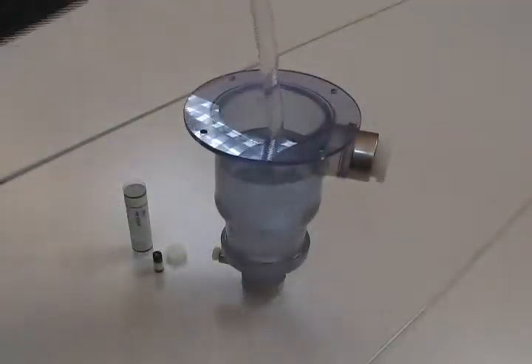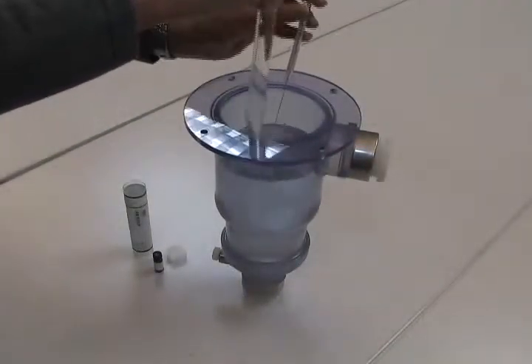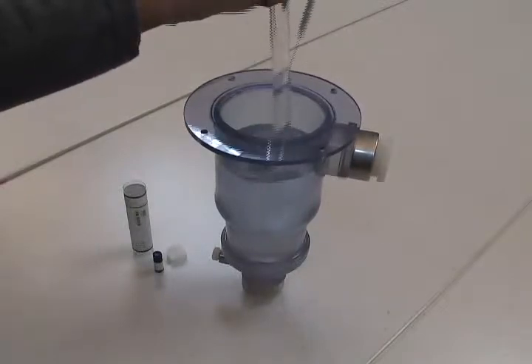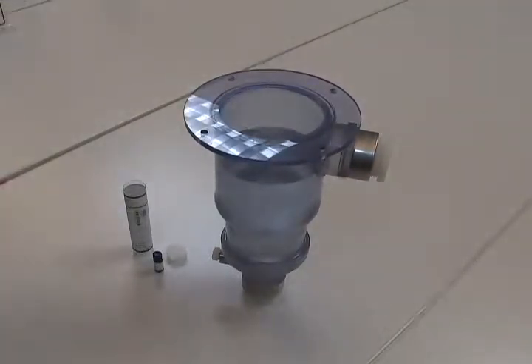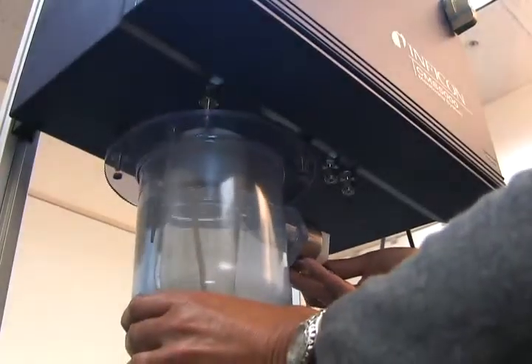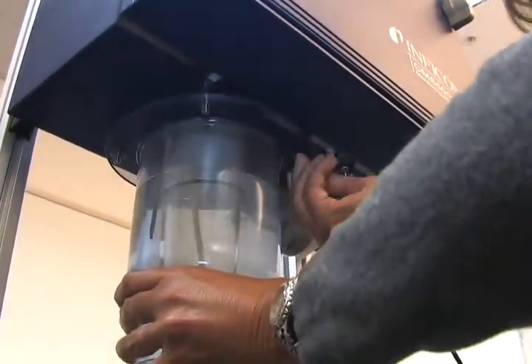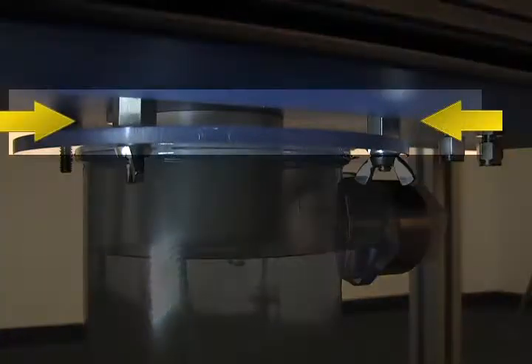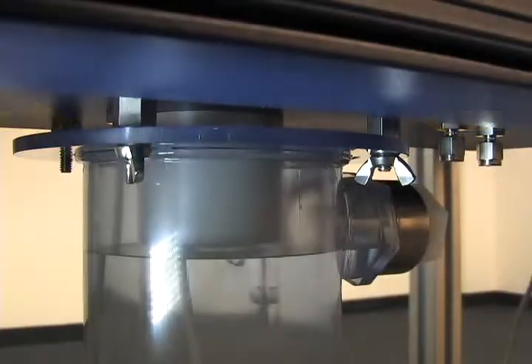To prepare the calibration standard, the 1-liter sample vessel is spiked with 2.5 microliters of the 19-compound calibration standard. Based on the initial concentration of the calibration standard, the resulting solution will contain 5 ppb of each compound. Ensure that the vessel is attached to all 4 standoffs on the bottom of the instrument. Wing nuts are used to secure the vessel in place. There is a small gap between the bottom of the instrument and the top of the sampling vessel. It is designed as an overflow mechanism to prevent water from being drawn up into the instrument.